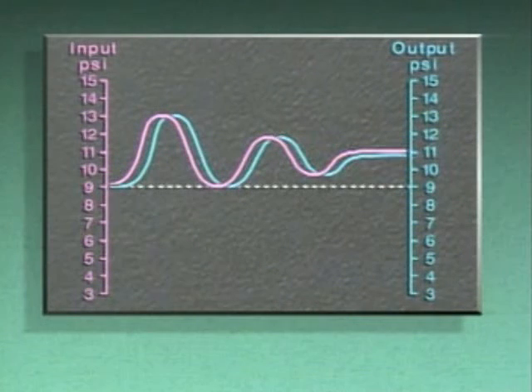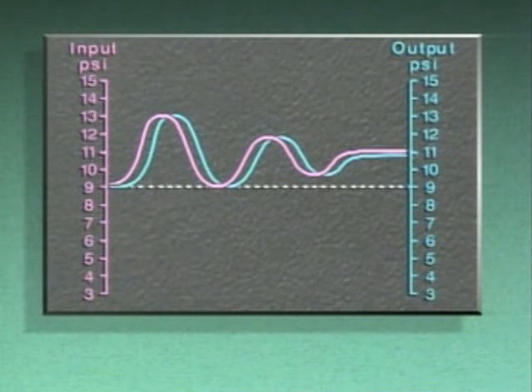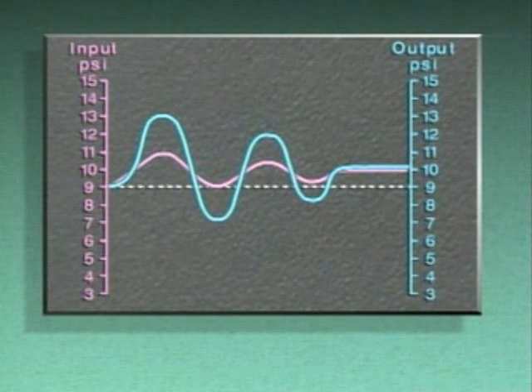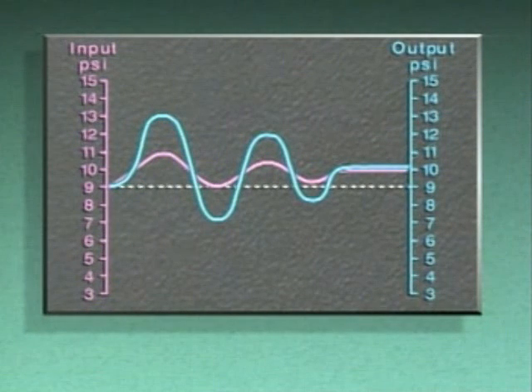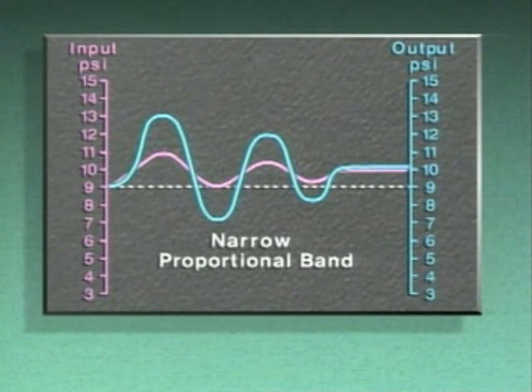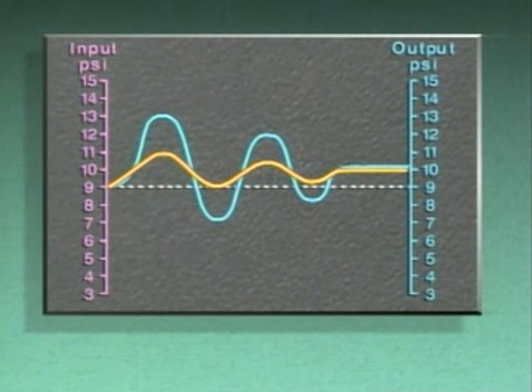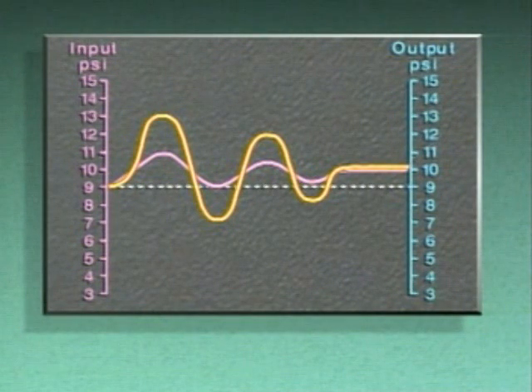The input and output signals on this graph show a 100% proportional band. Now, the signals on this graph show a proportional band that's less than 100%, otherwise known as a narrow proportional band. With a narrow proportional band, a small change in input to the controller produces a larger change in output.